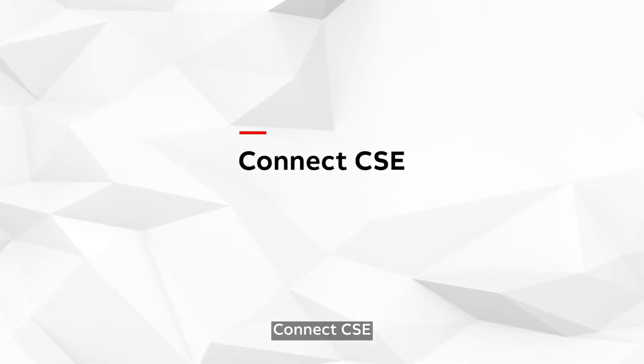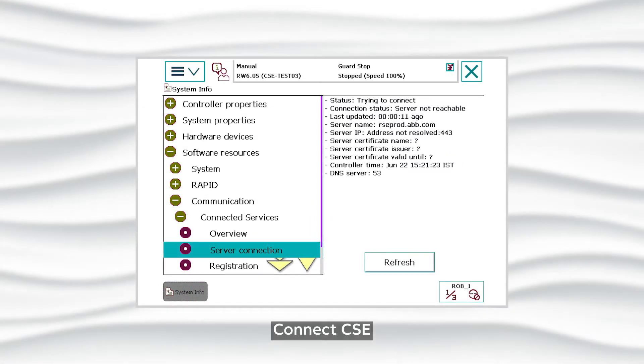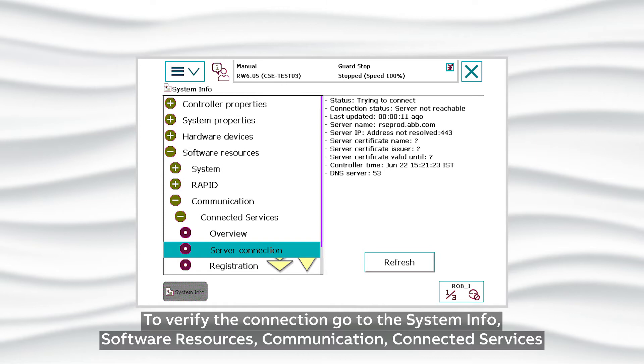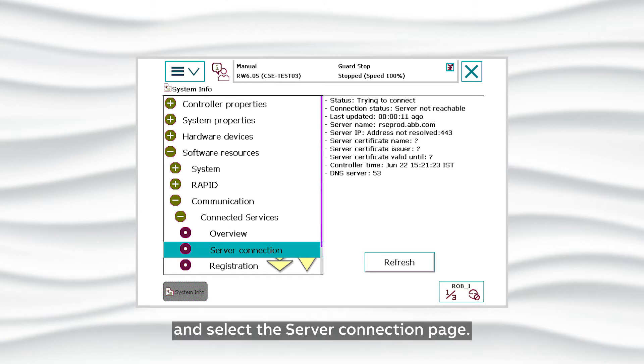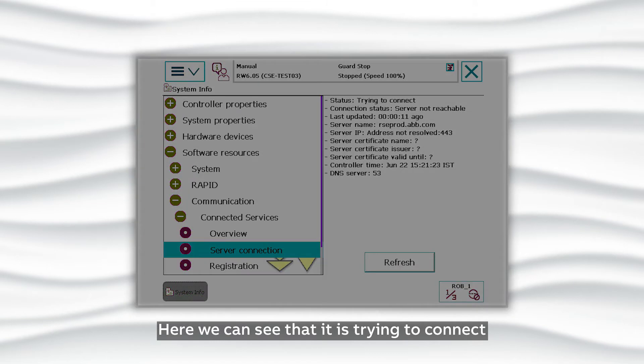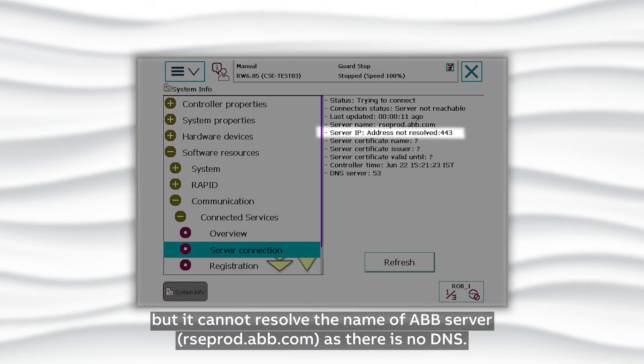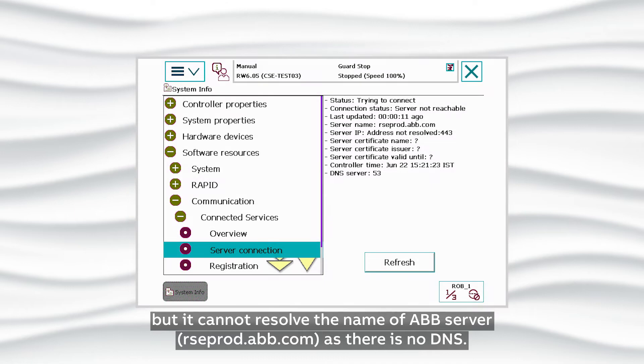Connect CSE. To verify the connection, go to System Info, Software Resources, Communication, Connected Services and select the Server Connection page. Here we can see that it's trying to connect but it cannot resolve the name of ABB Server, RSEprod.abb.com, as there is no DNS.